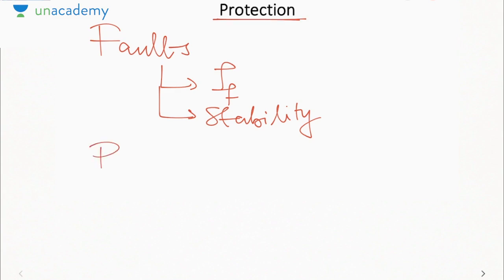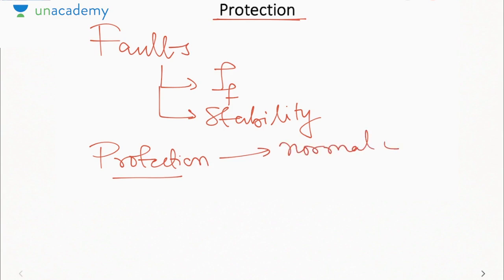So, the protection system has three functions. First of all, it has to detect between normal and abnormal conditions. What is meant by normal and abnormal? When the system is normally operating, heavy current may be due to extra load on the system. But if there is a fault, then a very high current flows. So, power system protection should be designed in such a way that it is able to discriminate which condition is normal and which is abnormal.